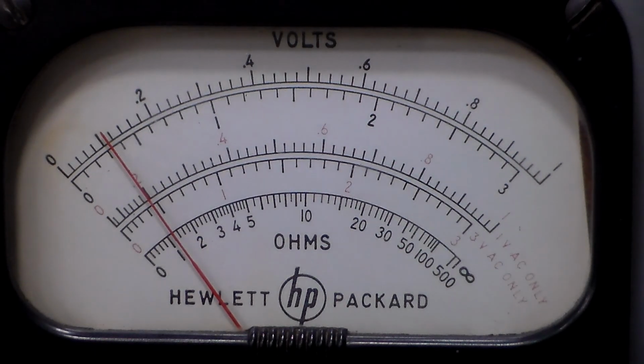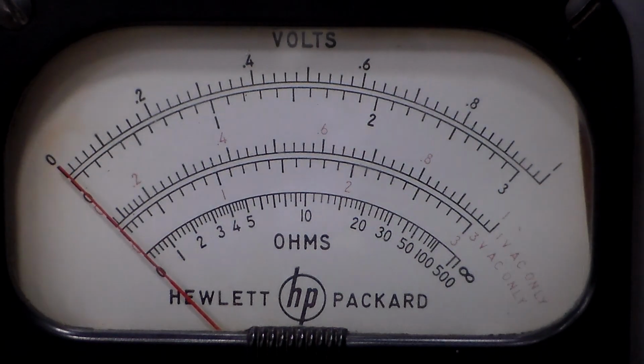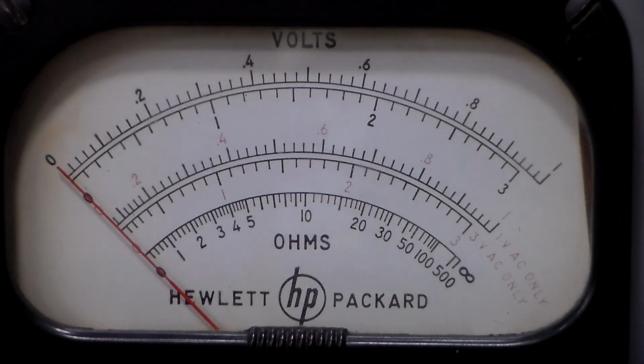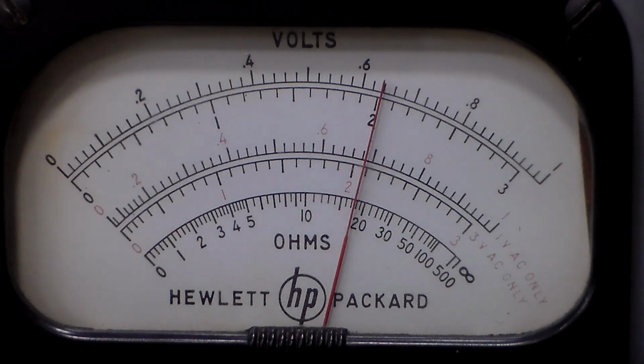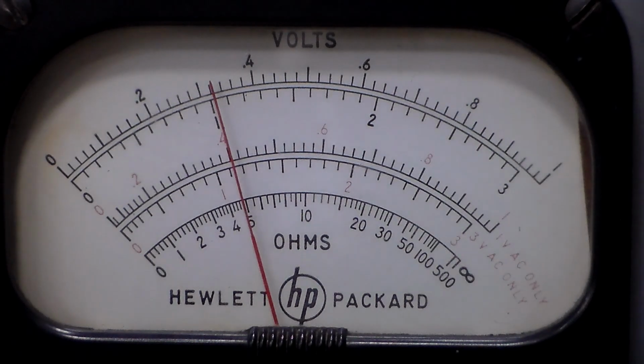Now if we go, say, to a different range, let's say, set this to 0 to start with. We'll change ranges. Let's go to 3 volts, and we'll put 3 volts in here, and it's reading 3 volts on the scale below. If I go to just a minute, we'll go back to 0. Just redo that. So if we say 2 volts, it's reading just a hair high, and 1 volt, and we're reading certainly better than 1% at that.